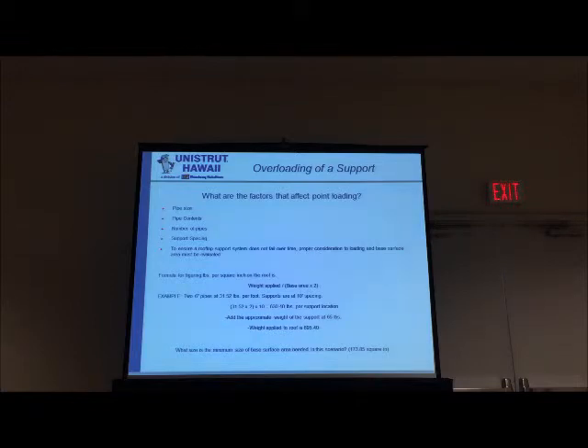This example is pipe, but you could use HVAC systems, you could use an air handler. You could mount your air handler on the roof using a non-penetrating support. There are other pieces of equipment, exhaust fans and so forth, that you can load on your roof, that again, you're going to need to know what the weight is, how many of them you need to support, and then how you can design an adequate support for all of that different type of service.